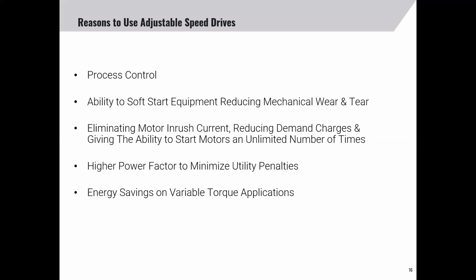Right. This is Daniel, and I'd like to add on to something that John mentioned. He mentioned the inrush current of the motor, and yes, that is a drain on the energy system, but it also heats up your motor. And most motors, when started across the line, are rated with so many starts per hour. When you remove that violent inrush, you're able to start your system multiple times a day, multiple times an hour, without ever having to worry about excessive heating, because you've never exceeded the full load amps rating of the motor.